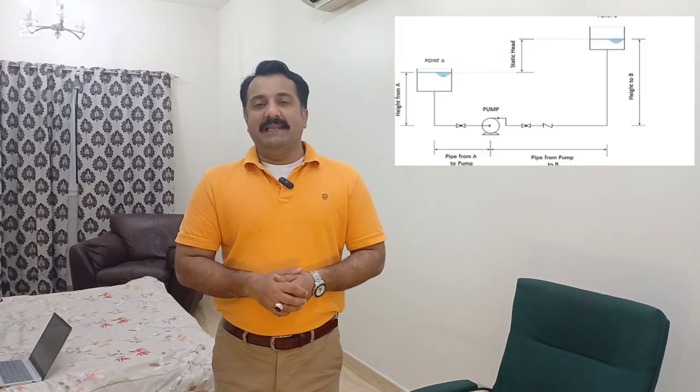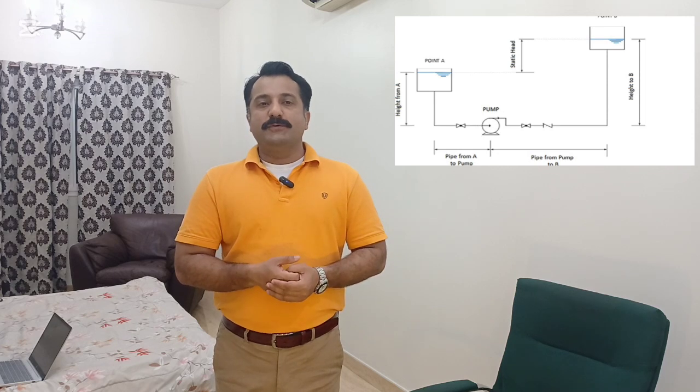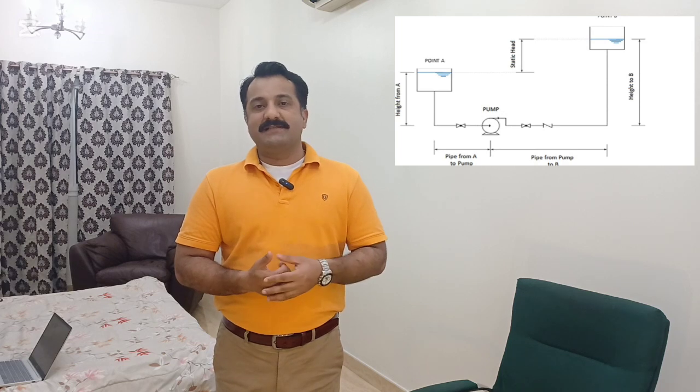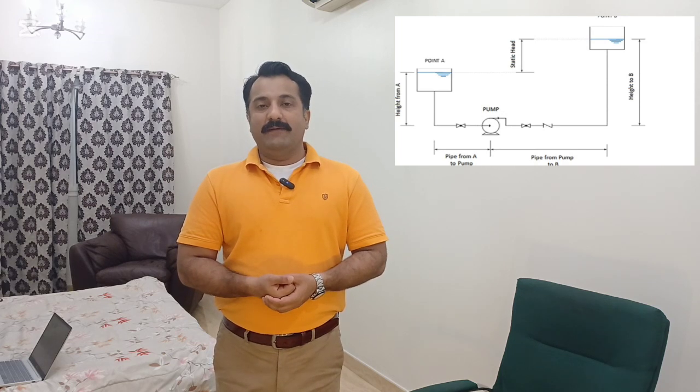You have to measure the tie-in points, distance and elevation also. Most of the people do not measure the elevation. Elevation is more important to perform hydraulics, especially for liquid lines, or pump discharge line or even suction line. We have to see NPSH, discharge pressure and losses. So elevation for a process engineer is very important. Nozzle elevation, how high it is from the ground level, and so on. So you have to cover everything according to your project requirement during the site visit.